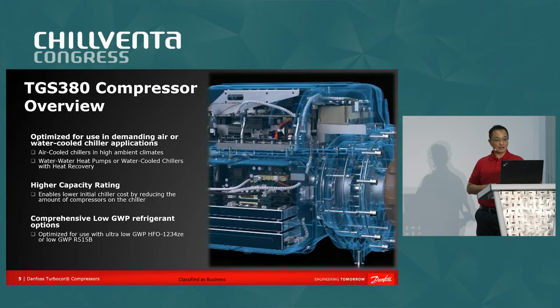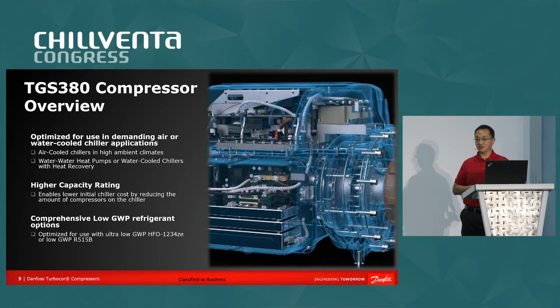On water-cooled chiller applications, this is optimized for use in heating or water-to-water heat pump applications or water-cooled heat recovery type of applications. And most importantly, this new compressor offers much higher capacity ratings than our previous compressors that can be utilized in high lift applications. And then lastly, this compressor utilizes all of our low GWP refrigerant offering that's available today, specifically HFO 1234ZE and R515B.